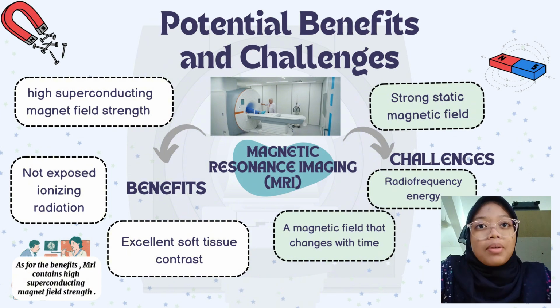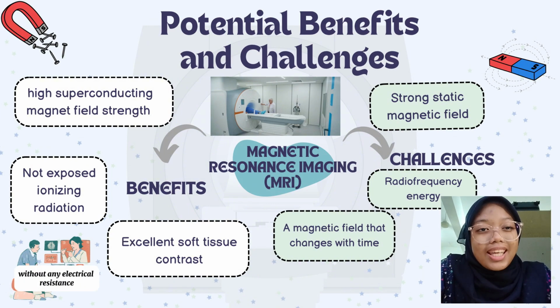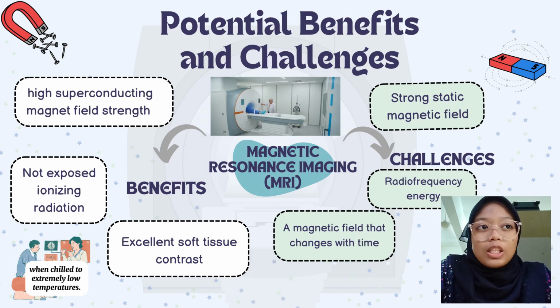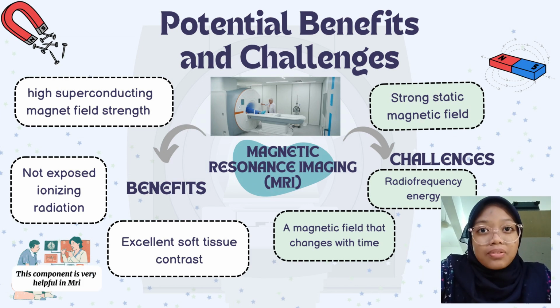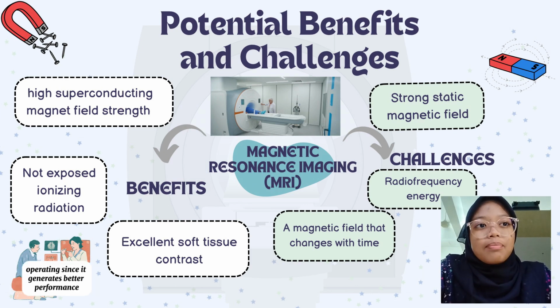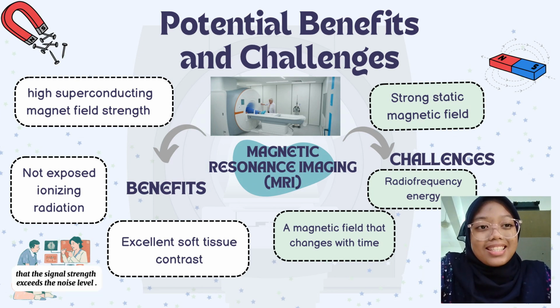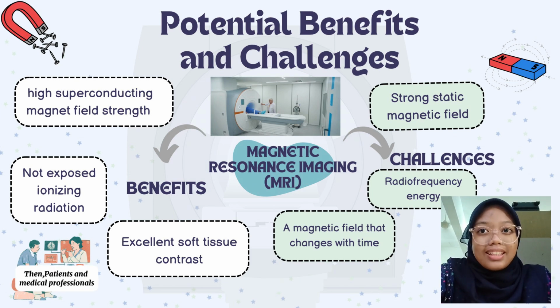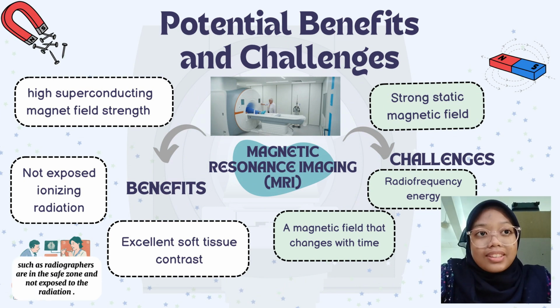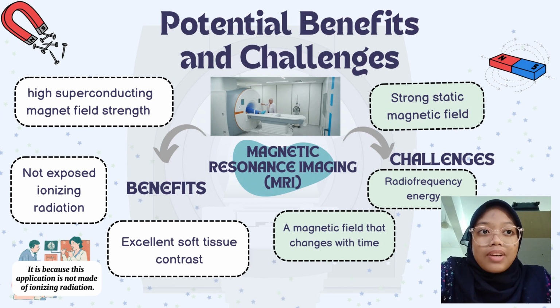As for the benefits, MRI contains a high superconducting magnetic field strength. It aids in producing a magnetic field without any electrical resistance when chilled to extremely low temperatures. This component is very helpful in MRI operation since it generates better performance, such as a high signal-to-noise ratio, which shows that the signal strength exceeds the noise level. Then, patients and medical professionals such as radiographers are in a safe zone and not exposed to radiation, because this application does not use ionizing radiation.